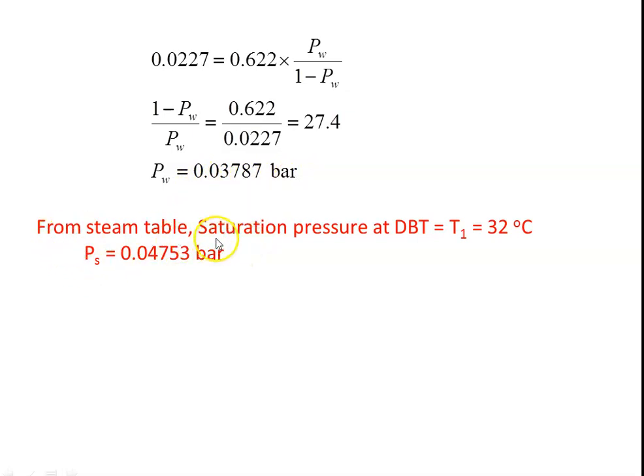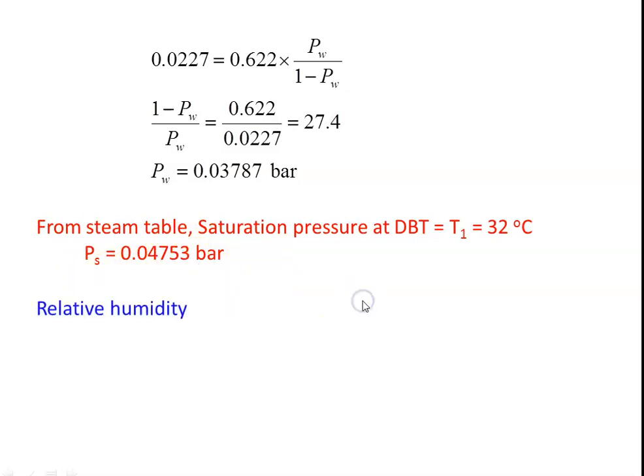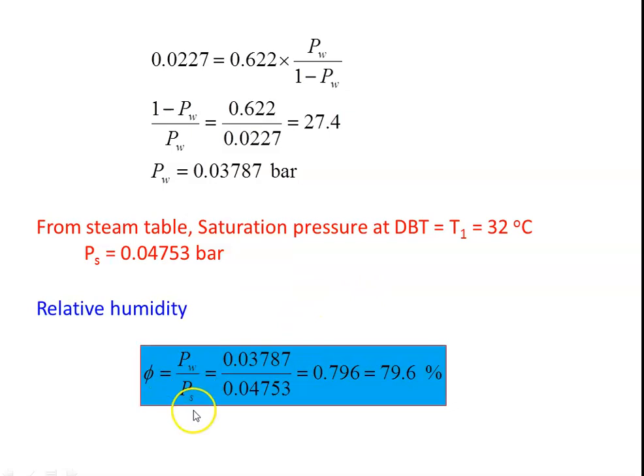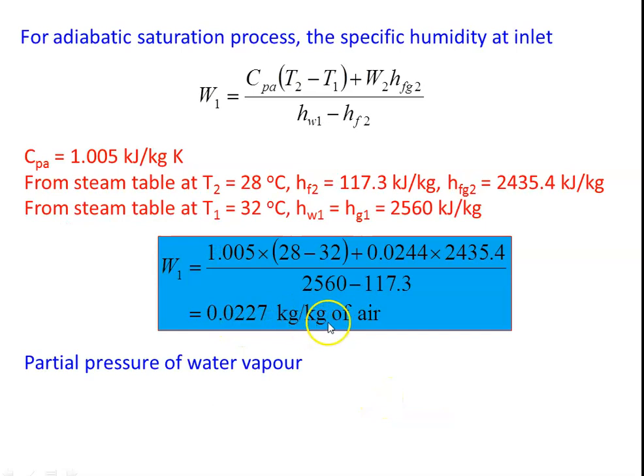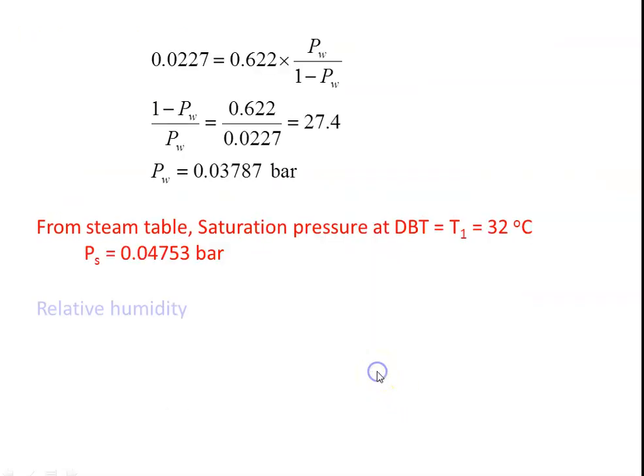From the steam table, the saturation pressure at dry bulb temperature T1 = 32°C is PS = 0.04753 bar. The partial pressure of water vapor is 0.03787 bar and the saturation pressure is 0.04753 bar. Relative humidity φ = PW / PS = 0.03787 / 0.04753 = 0.796 = 79.6%. So the relative humidity is 79.6% and specific humidity is 0.0227 kg per kg of air. That is the answer for this problem.